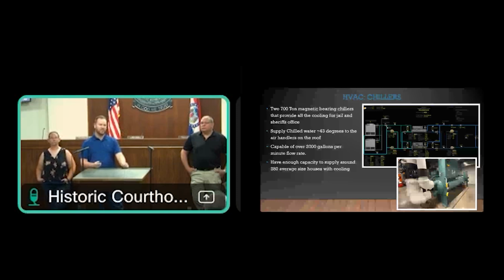One of the next big things would be heating and cooling. The jail has 2 700-ton magnetic bearing chillers. With all the equipment, you'll see a lot of redundancy at the jail, so that there's hopefully no downtime. One chiller is capable of cooling the whole jail, so while one is down getting maintenance, the other can run to provide the cooling. This unit supplies 43-degree water out to the air handlers, which we'll talk about in a little bit, and it's capable of producing over 2,000 gallons per minute flow rate of that 43-degree water. As a reference to size, we have enough capacity to supply around 280 average size houses with cooling. So it's a very large system.